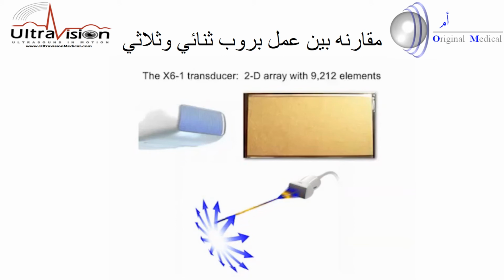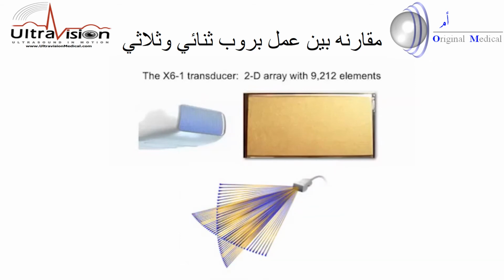One of them is in a conventional B-mode, but also, of course, because you can steer the beam in the elevation direction, that B-mode can be translated without moving the transducer, and indeed you can make two or many more simultaneous real-time B-mode images of adjacent slices. The transducer can also image in the orthogonal direction, and once again it can do that simultaneously with imaging in the long axis direction. And this simultaneous orthogonal imaging, where two B-mode planes at right angles to each other are presented together in real time, is one of the fundamental modes of imaging that the IU-22 provides with the X6-1 for abdomen and OBGYN applications, and it's called X-plane imaging.